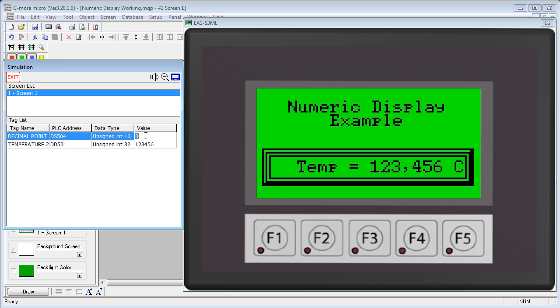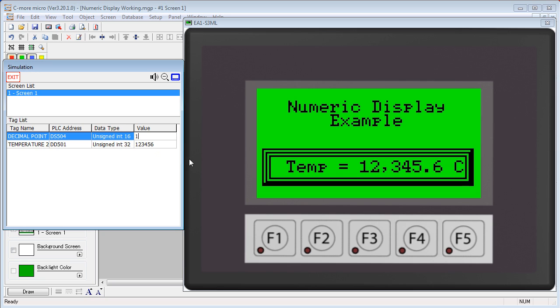And now if we move our decimal point to, say, position 3, that's exactly where it appears. How about position 5 or position 1? So now the PLC can automatically scale the results being displayed to the user on the fly as it's running.